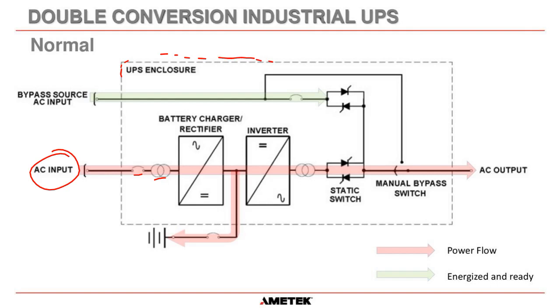That AC then goes into a rectifier battery charger, and the AC gets converted into DC. That DC keeps the batteries trickle charged, and it also supplies the DC in parallel to the inverter. And the inverter changes the DC back into AC through an output transformer, and then it goes through an output static switch, which then goes through the manual bypass switch.